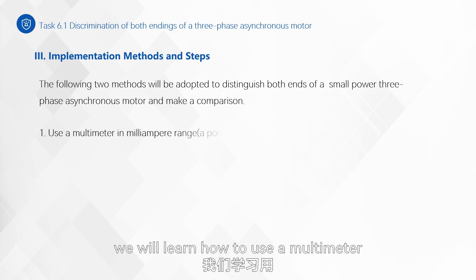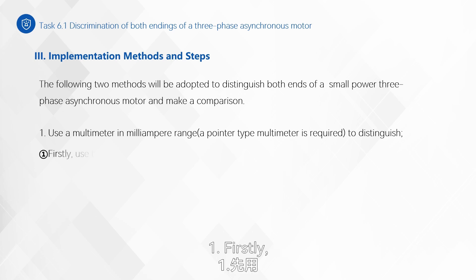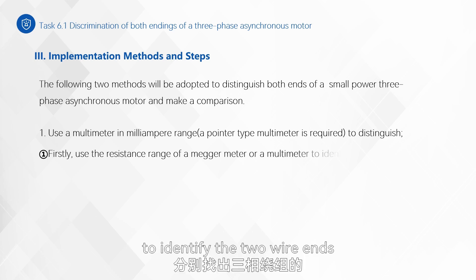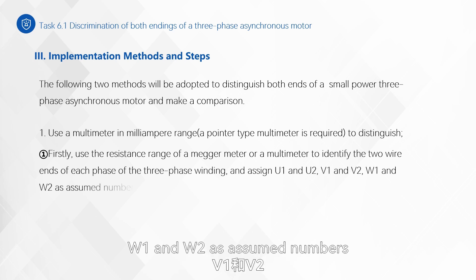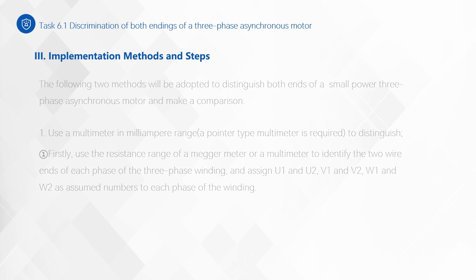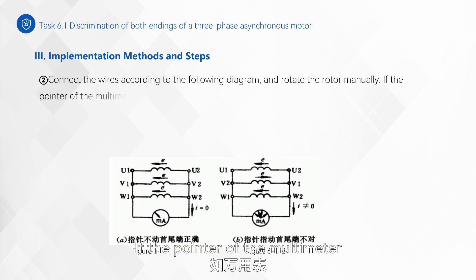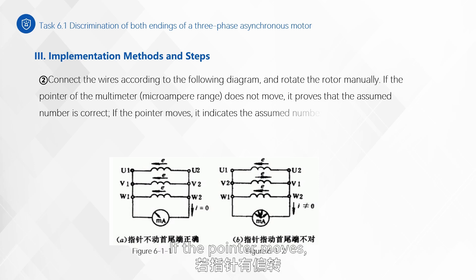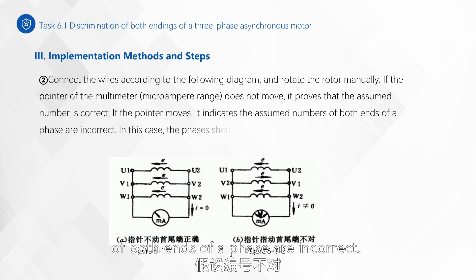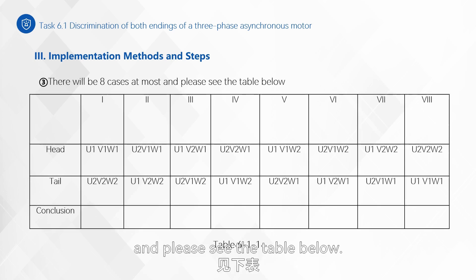Method one: use a multimeter in the milliampere range — a pointer-type multimeter is required — to distinguish. First, use the resistance range of a megger meter or multimeter to identify the two wire ends of each phase of the three-phase winding and assign U1 and U2, V1 and V2, W1 and W2 as assumed numbers to each phase. Second, connect the wires according to the diagram and rotate the rotor manually. If the pointer of the multimeter in the microampere range does not move, it proves the assumed number is correct. If the pointer moves, it indicates the assumed numbers of both ends of that phase are incorrect, and the phases should be readjusted and retested one by one until the numbers are correct. There will be eight cases at most — please see the table.